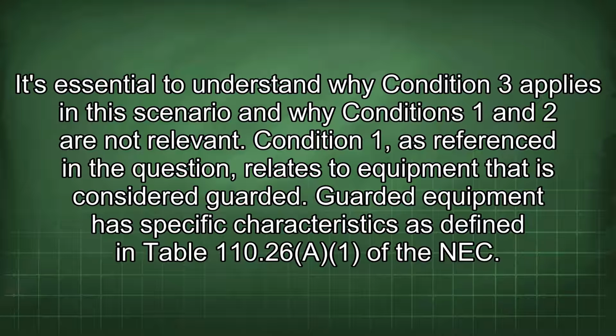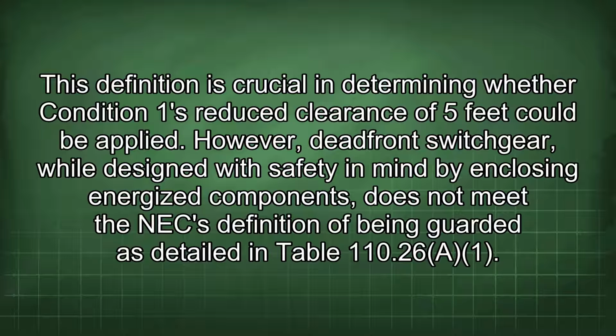Guarded equipment has specific characteristics as defined in Table 110.26(A)(1) of the NEC. This definition is crucial in determining whether Condition 1's reduced clearance of 5 feet could be applied. However, dead-front switchgear, while designed with safety in mind by enclosing energized components, does not meet the NEC definition of being guarded as detailed in Table 110.26(A)(1).